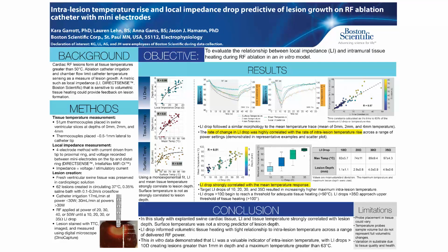So overall, we found that local impedance is a valuable indicator of intralesion temperature and lesion dimensions.